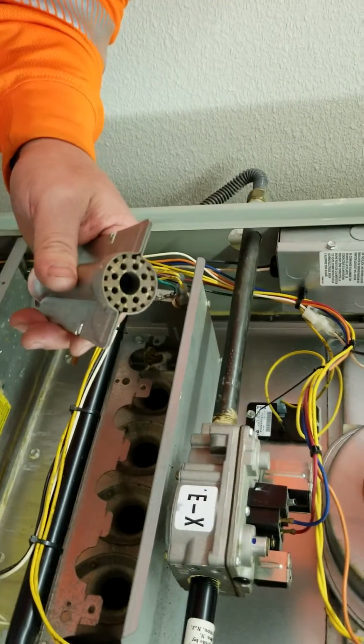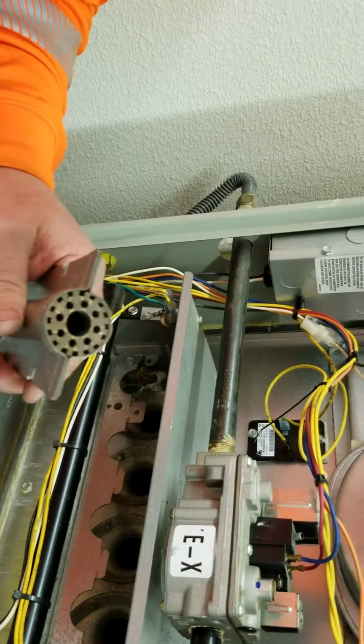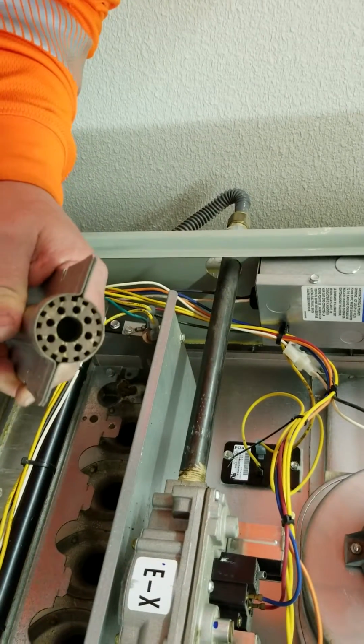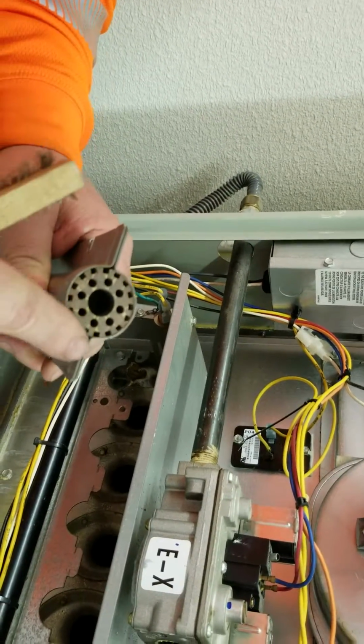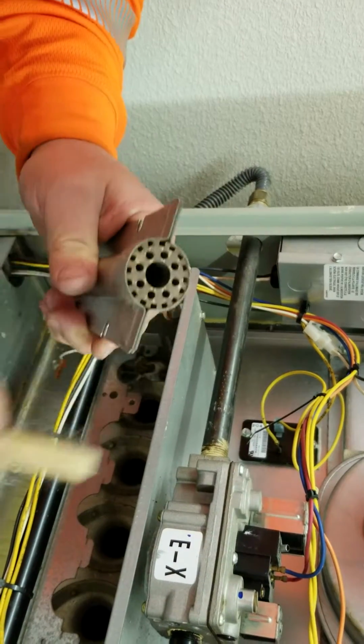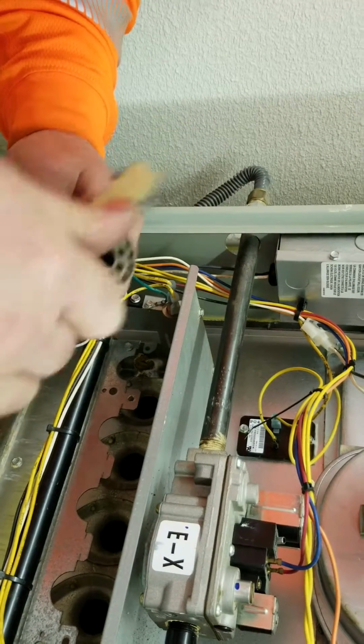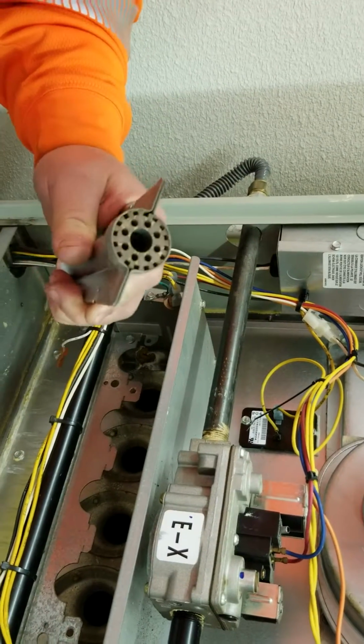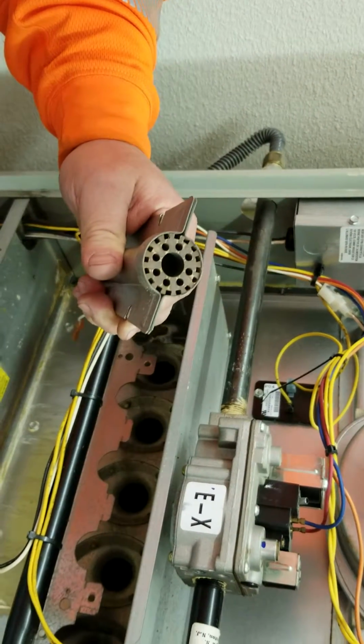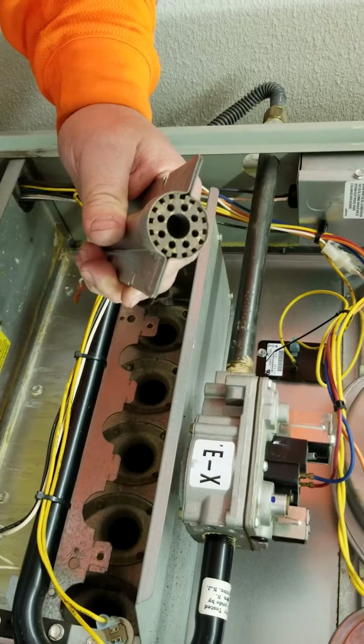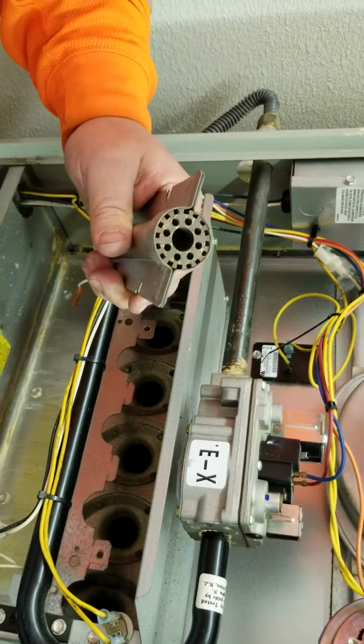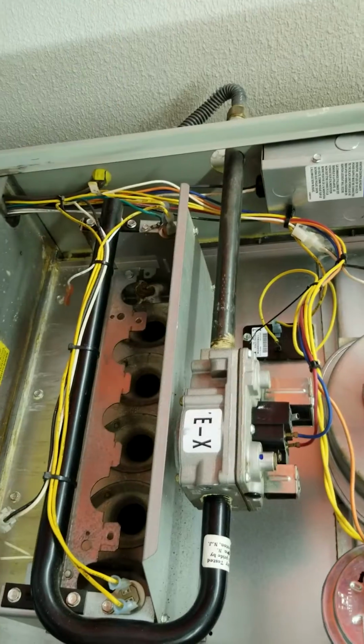Okay, burner face. You want to clean any debris off the burner face, paying close attention to the runners on the sides, because that's where the flame travels from one burner to the next. And eventually, the flame has to make the connection all the way across in order to prove so that the furnace will stay lit. So go ahead and continue cleaning your burners, Damien.